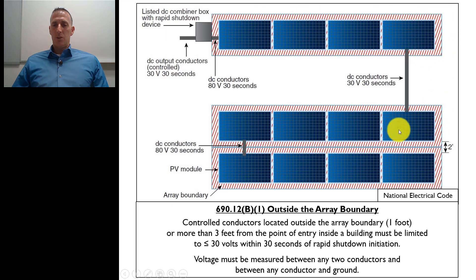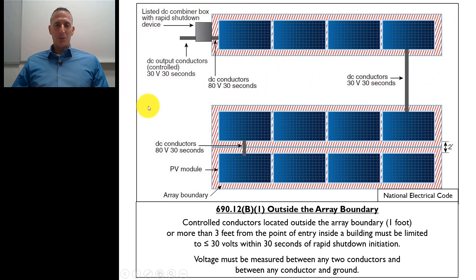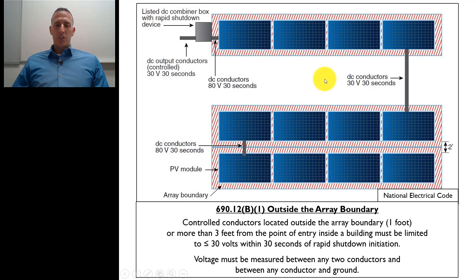Here's the array, and the array boundary extends a foot in each direction. Those controlled conductors located outside the array boundary — anywhere outside that one-foot boundary, or more than three feet from the point of entry inside a building — once it's more than three feet inside the building, all of those conductors must be limited to less than or equal to 30 volts within 30 seconds of the rapid shutdown initiation.